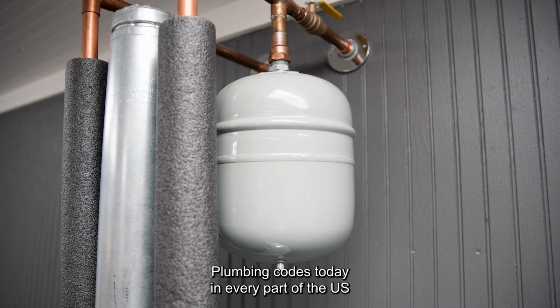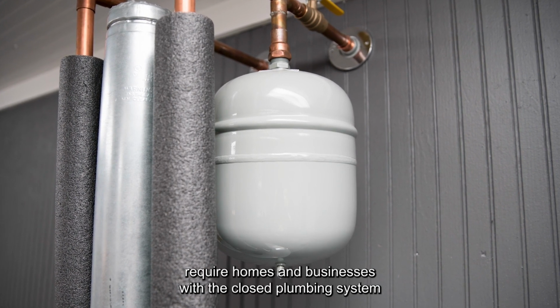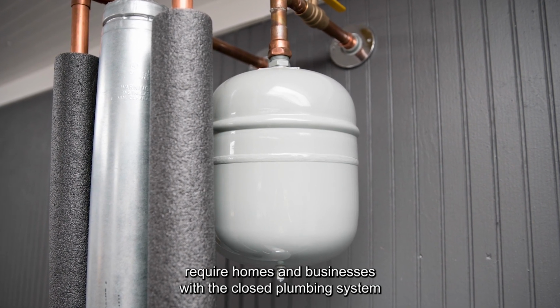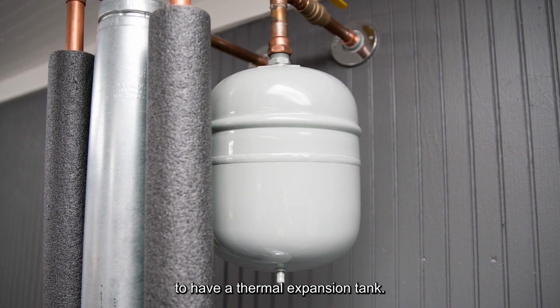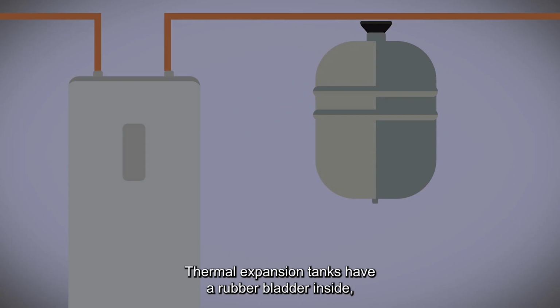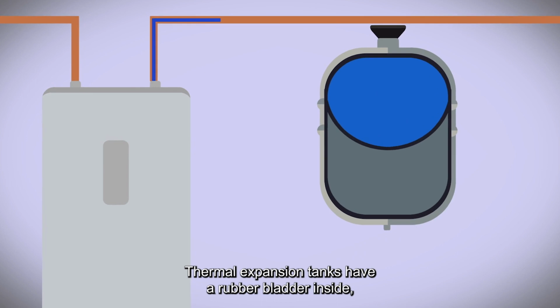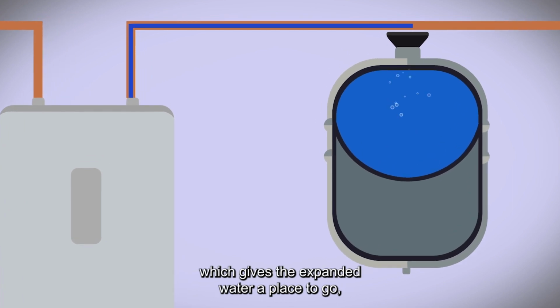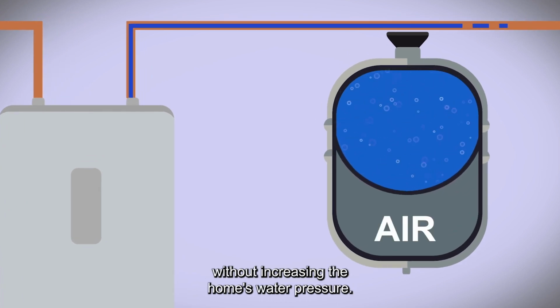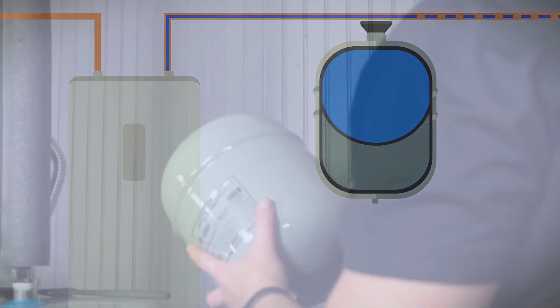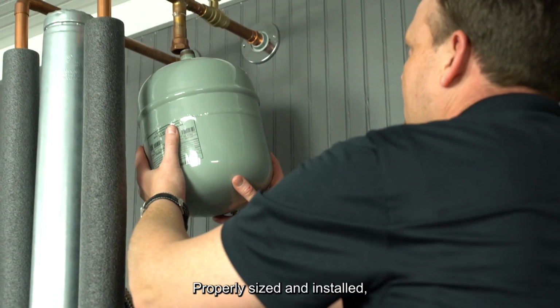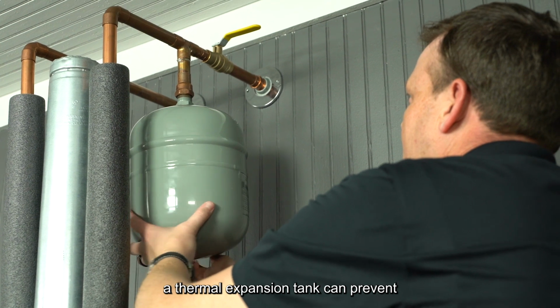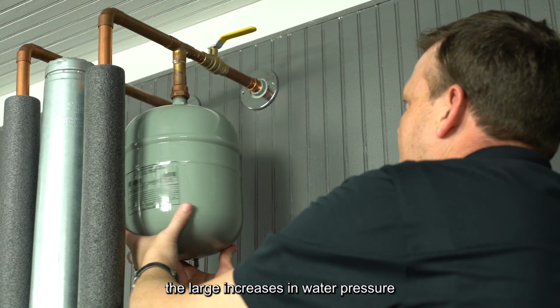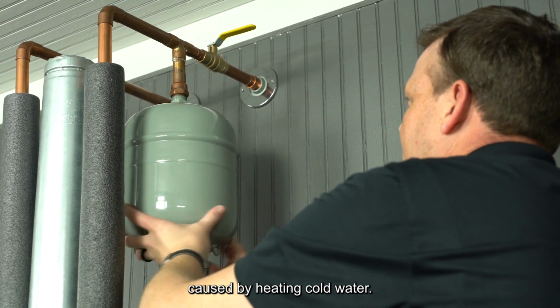Plumbing codes today in every part of the U.S. require homes and businesses with a closed plumbing system to have a thermal expansion tank. Thermal expansion tanks have a rubber bladder inside, which gives the expanded water a place to go without increasing the home's water pressure. Properly sized and installed, a thermal expansion tank can prevent the large increases in water pressure caused by heating cold water.